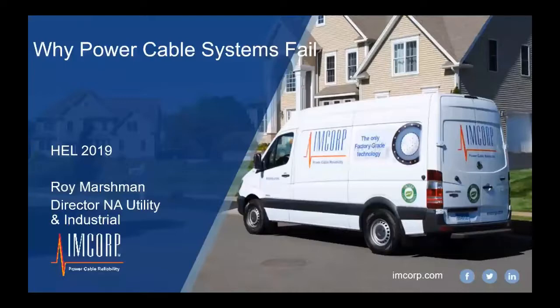My name is Roy Marshman. I'm responsible for utility and industrial sales for IMCORP. For those who aren't familiar with IMCORP, we provide a 50-60 hertz partial discharge test offline. It's equivalent to what the factory does on components and cables, meeting IEEE or ICEA standards.